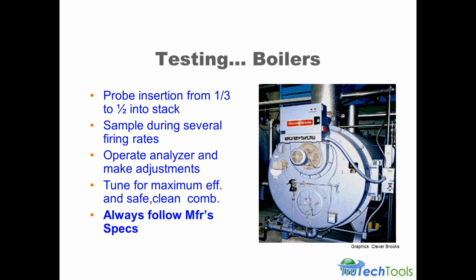When we get into testing larger equipment, the parameters change a little bit. The probe insertion place now is about 1/3 to 1/2 of the way into the stack. You're not so much looking for that core sample in this situation, but you do want to hit a consistent, repeatable point. You're going to have to sample several firing rates, because that's the nature of the beast when you have these larger equipment. In many cases you'll operate the analyzer, turn the analyzer off, make some adjustments, and go back and continue an iterative process. In this case you're tuning for maximum efficiency, safe combustion, and clean and efficient combustion.